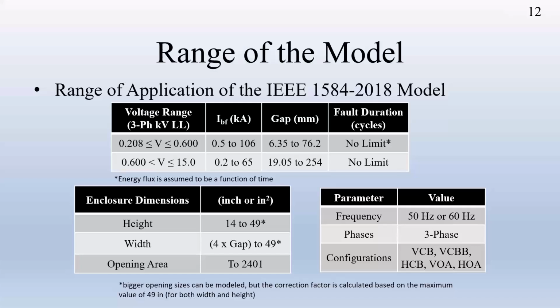And then also you have a five configuration. We call it the VCB. It's a vertical electrode in the cubic box. During the test we used the cubic box, so we just named it the cubic box. It's a metal enclosure. VCBB is the vertical electrode in the metal enclosure with a barrier. HCB is the horizontal electrode inside the metal enclosure, VOA is the vertical open air, and HOA is the horizontal open air.